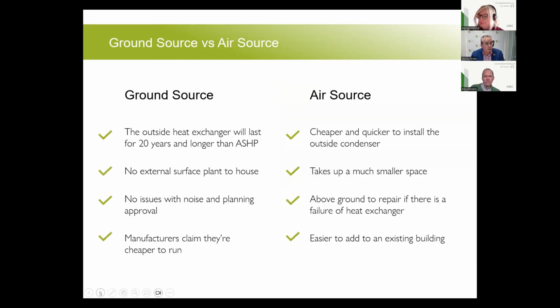So I just want to do a quick comparison of ground source and air source criteria. I have been accused in the past of being a little bit too pro air source and not as positive about ground source. The manufacturers will report that ground source is more efficient than an air source heat pump, where they would typically achieve COPs of 3.5 to 3.8 with a 50-degree temperature feeding their underfloor heating, compared, say, to an air source heat pump at -4, -5, where it may be down as low as 3 to 1. So in that scenario, at 50 degrees, clearly an air source heat pump is not as efficient.